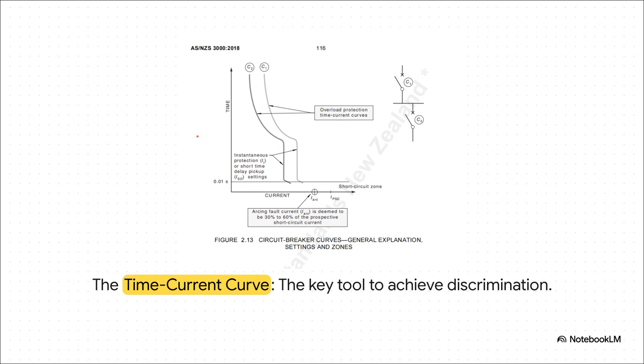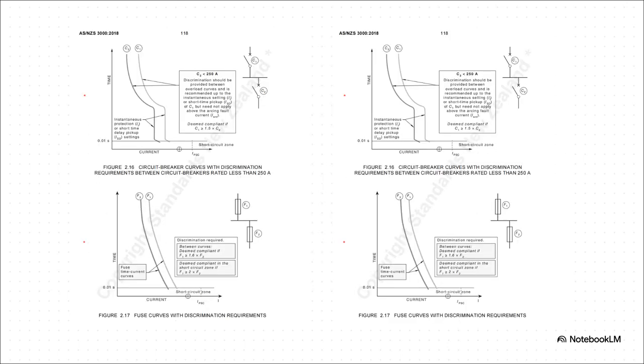To get discrimination, you lay the curves for your upstream and downstream devices on top of each other. You have to make sure there's always a clear gap, a white space, between them, so you know for sure the downstream device will always be faster on the draw. And get this, the rules are different depending on what you're using. On the left, for common circuit breakers, there's a pretty simple rule of thumb. Just make sure the upstream breaker is at least 1.5 times bigger than the downstream one.